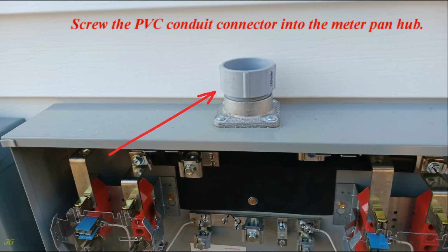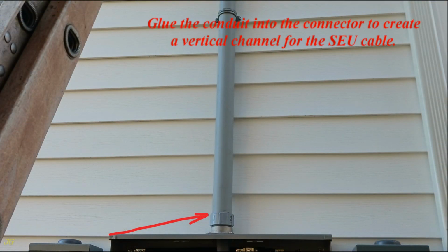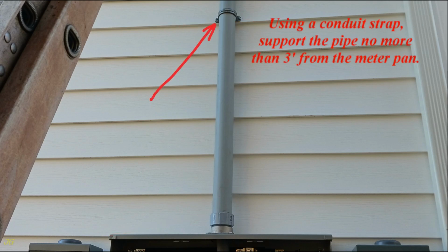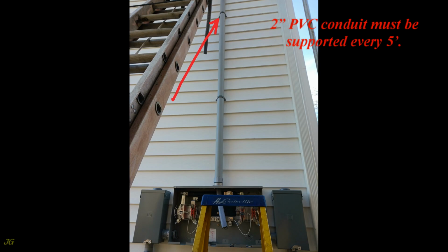Screw the PVC conduit connector into the meter pan hub. Glue the conduit into the connector to create a vertical channel for the SEU cable. Using a conduit strap, support the pipe no more than 3 feet from the meter pan. 2 inches PVC conduit must be supported every 5 feet.